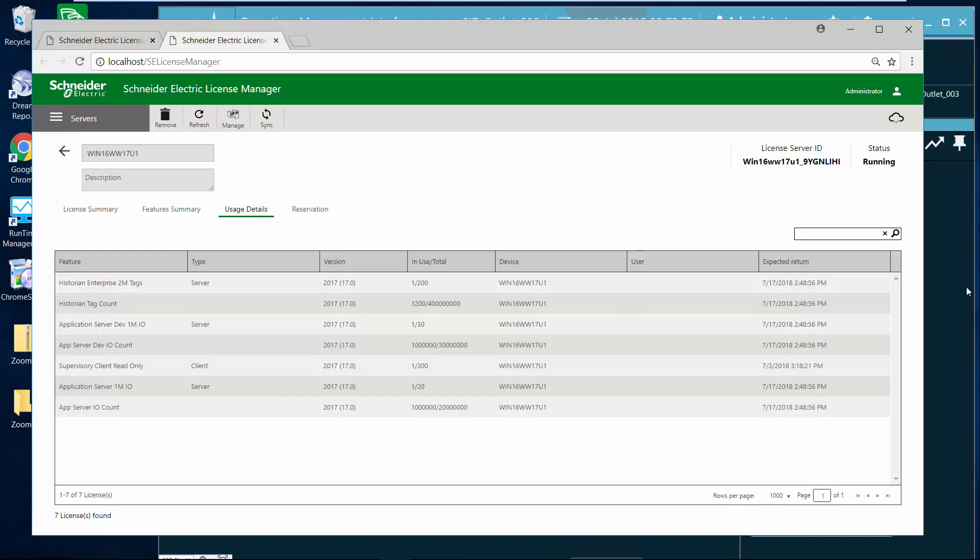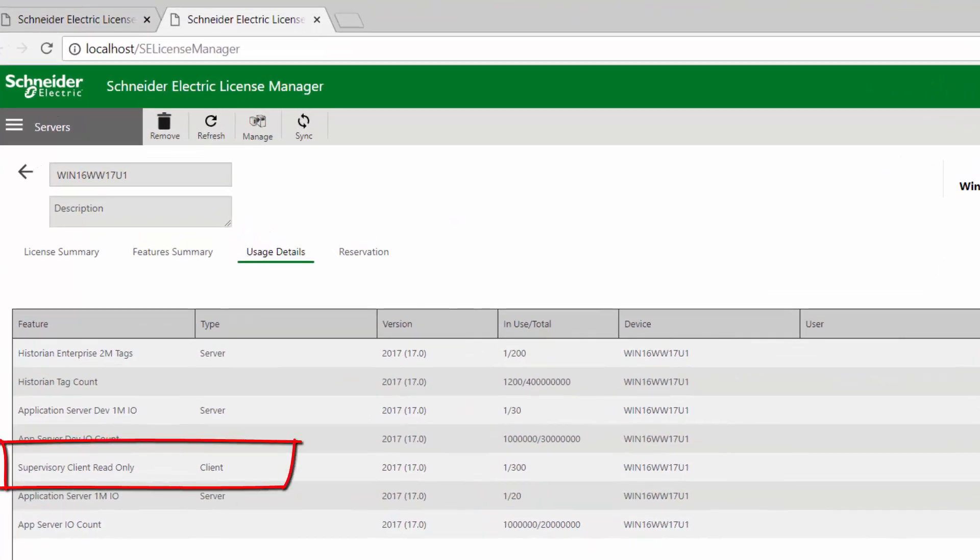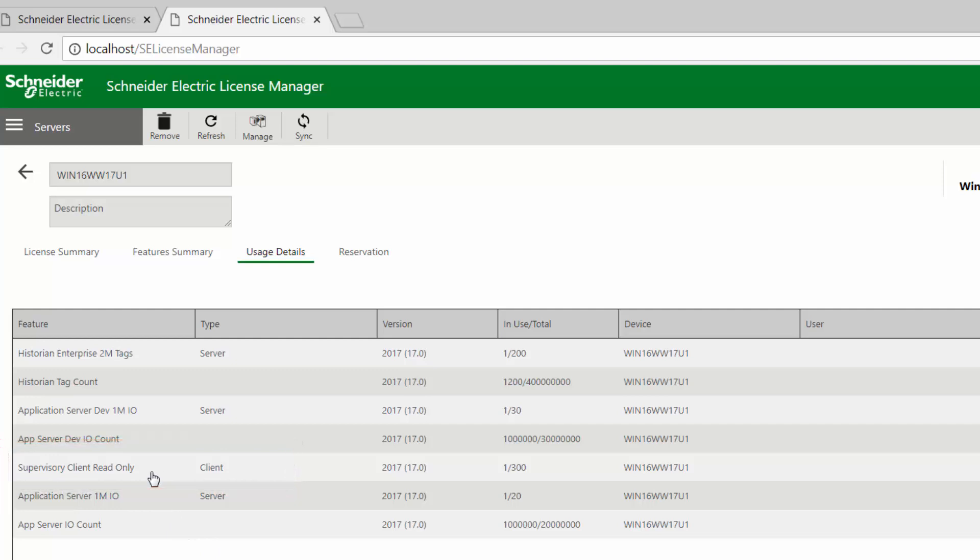So I closed down my full control OMI application now. So I only have the read-only instance running. If I look at the license manager, you can see that the supervisory client read-only license was checked out. So when I run an OMI with that flag that I pass in as read-only, it's going to consume a read-only license.